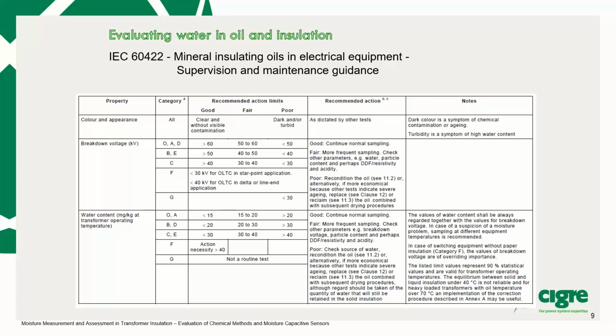You find it in any IEC standard, especially the standard IEC 60422. Of course, Karl Fischer measurement is still very important and widespread, that's why you have key values for water in mineral oil in such a standard. But at the same time, you see a lot of recommendations and messages telling you to always regard the moisture in the liquid together with the breakdown voltage, because they are very interdependent.